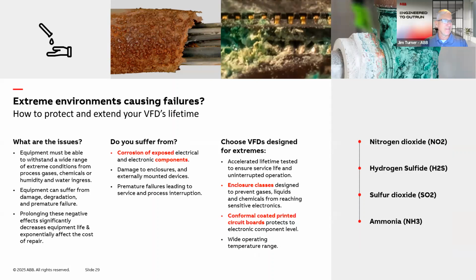Every water plant that I visit, and here's another big issue, it's the destructive airborne chemicals and contaminants. All those that are listed, along with maybe chlorine and so forth, all have a destructive negative impact on printed circuit boards and other critical components in your facility. These silent killers, you never know when they're going to strike. And what makes it worse is all the high humidity that you typically have in these water plants, combined with these corrosive gases, making a nasty environment that you need to take countermeasures against.